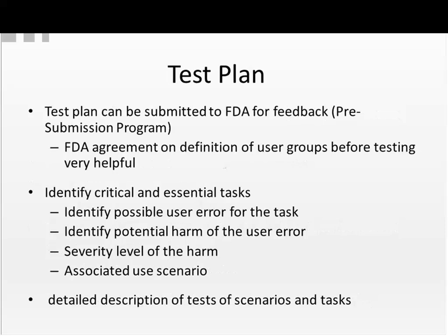As part of a pre-submission program, you can submit your test plan to the FDA for feedback. This is a very good idea, especially to get the FDA agreement on your definition of user groups, because 15 people adds up very easily to quite large groups.